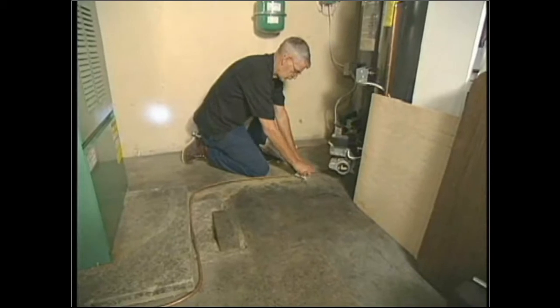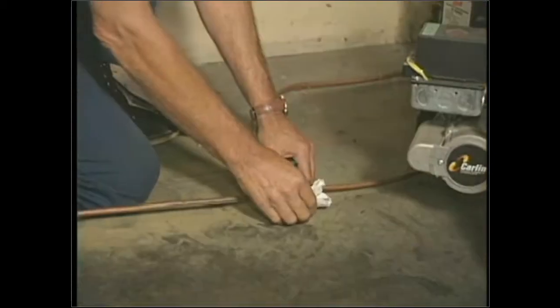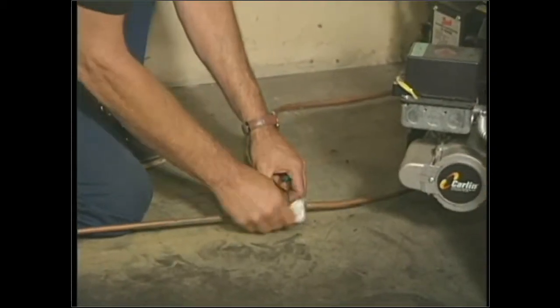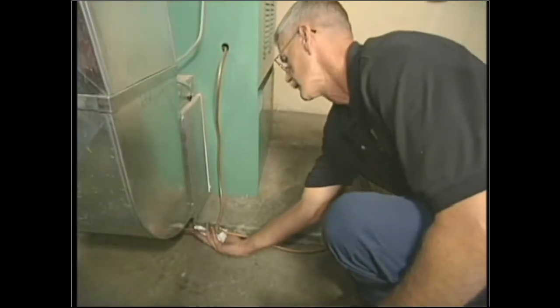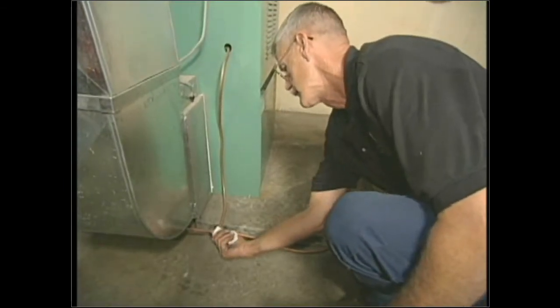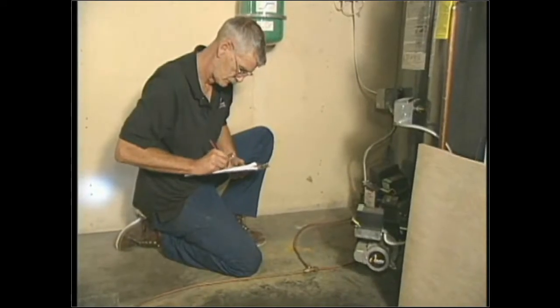You visually inspect underneath the tank to see if there's any pinholes in the tank that are dripping down, that can create a problem. And then I'll chase that system, just like we did with the natural gases and the LPs. I'll chase it all the way from the tank to the termination at the furnace, or if it passes on through, like in this case, I'll check all of them too. You're also looking for kinks and bends.